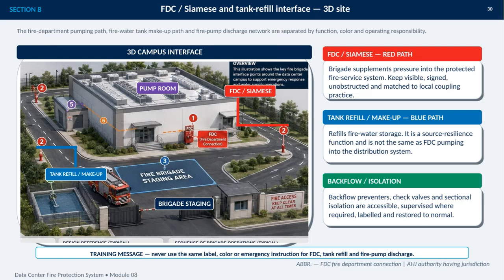the tank refill system. The central message is that these functions must remain clearly separated by purpose, color, labeling, and operating responsibility. The FDC and Siamese connection support Brigade pumping into the protected fire service distribution system. They should remain visible, clearly signed, unobstructed, and compatible with local coupling practice.